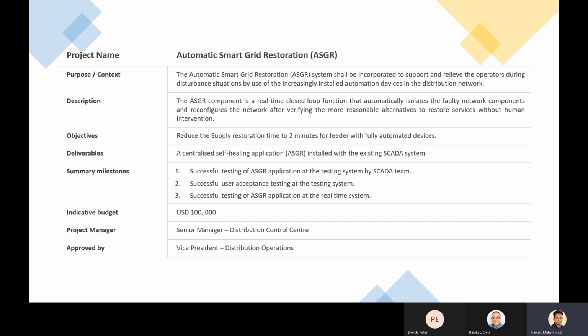It will take the data from those devices, and it will normalize the network based on the alarms. So this is a real-time closed loop function that automatically isolates the faulty network components and reconfigures the network after verifying the more reasonable alternative to restore services without any human intervention. According to our KPI for the entire organization, the objective of this project is to reduce the supply restoration time to 2 minutes for feeder with fully automated devices. And at the end of the projects, we will have a centralized self-healing application installed at the existing SCADA system.